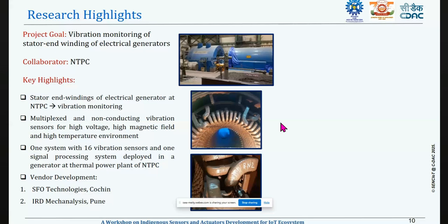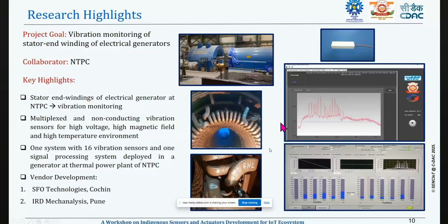The drawback was that electrical sensors could not be used here, because in an electrical generator there will be EMI interference and it will not give the correct signal. So for this, 16 vibration FBG sensors and one signal processing system have been deployed in a thermal power plant in NTPC for an electrical generator, and these are the signals we get. Wherever they find the vibration is above a safety limit, they can stop it right there and go for maintenance, tighten the windings, and prevent untimely catastrophic failure.